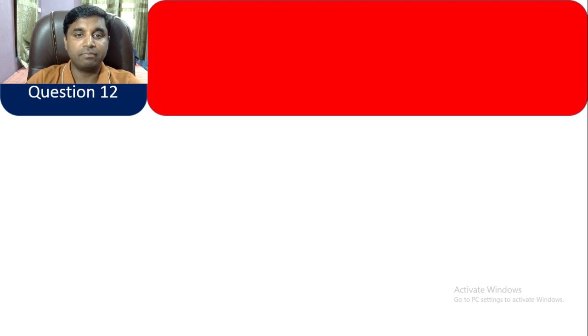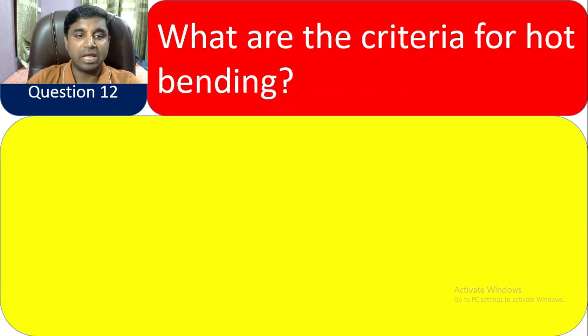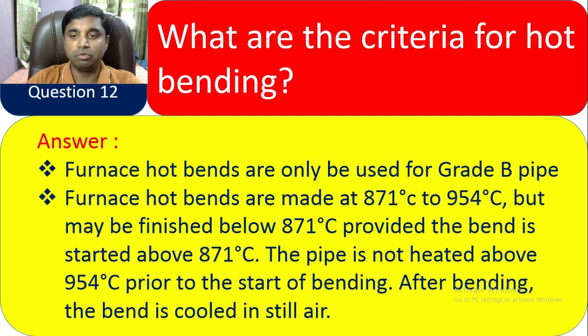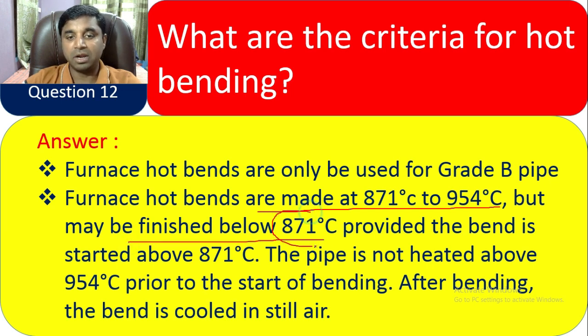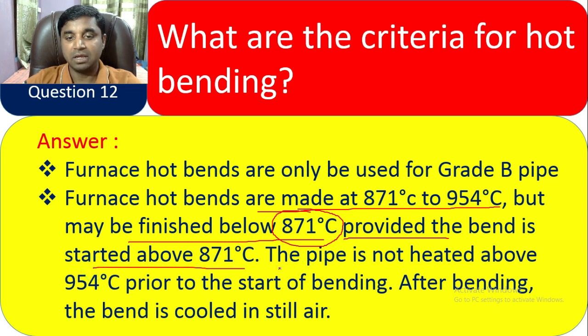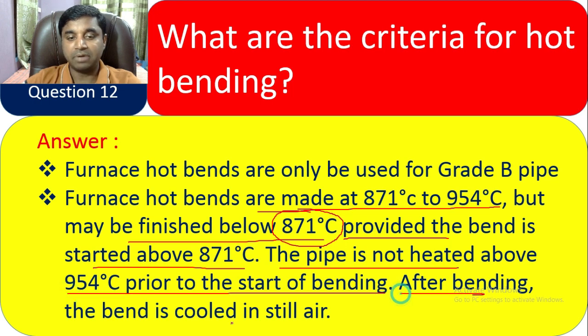Question 12: What are the criteria for hot bending? Furnace hot bends are only used for Grade B pipe. Hot bends are made at 871°C to 954°C, but may be finished below 871°C provided the bend is started above 871°C. The pipe is not heated above 954°C prior to the start of bending. After bending, the bend is cooled in still air.